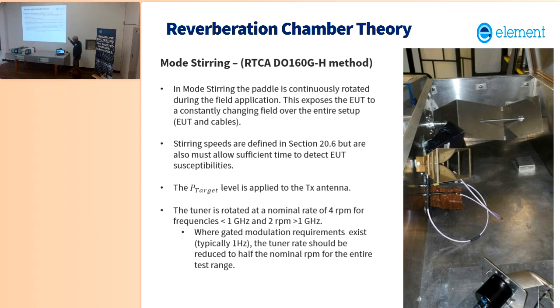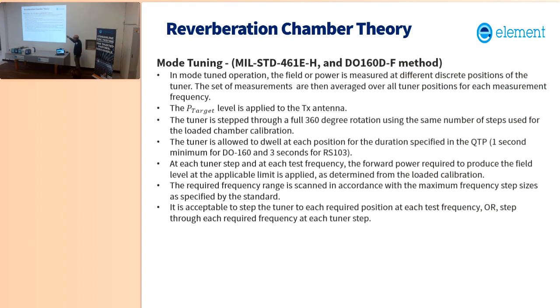So for mode tuning, whether you're doing 461 or older versions of DO-160, you're applying that calculated power level to the antenna, what you need to produce your field, and you're stepping the tuner through the same number of steps that you used during the loaded chamber calibration. We've got field uniformity verified here at 10-degree steps, right? So you've got to take at least the same number of steps that you took during the field uniformity validation. You can take more, but you take the same number of steps during the loaded chamber calibration as during the test, okay? So you can take 72 steps instead of 36, but you have to do that for both the loaded measurement and the test.